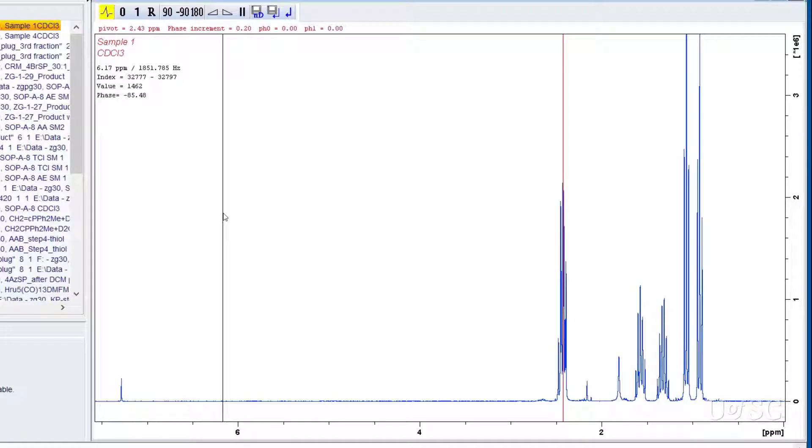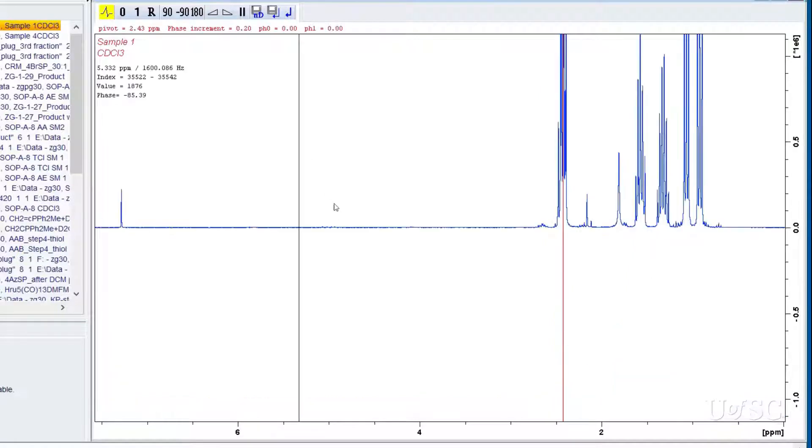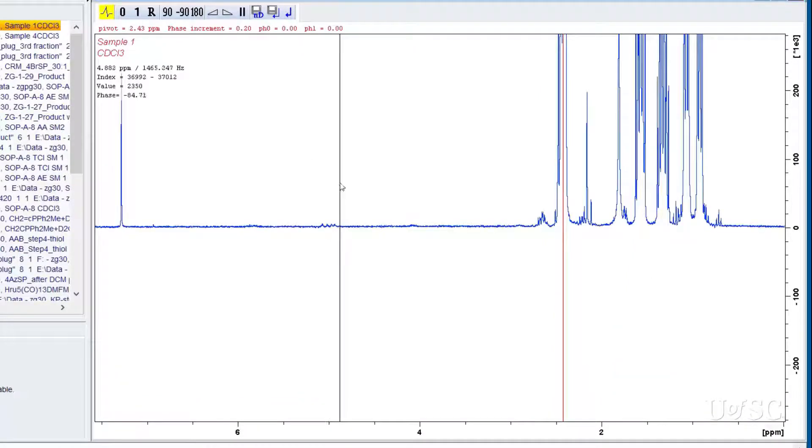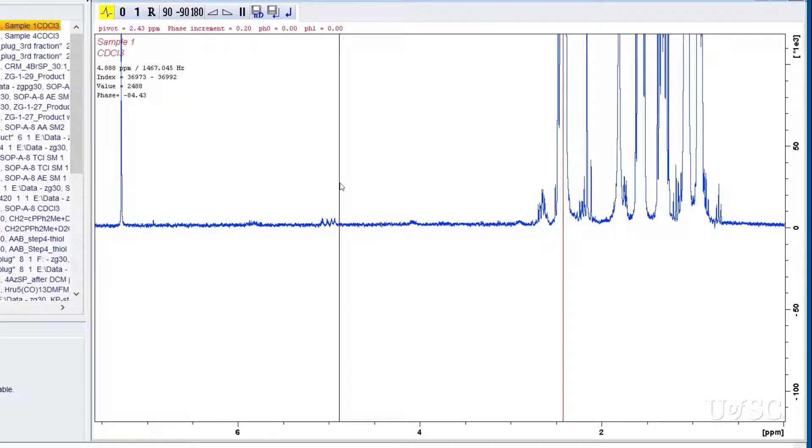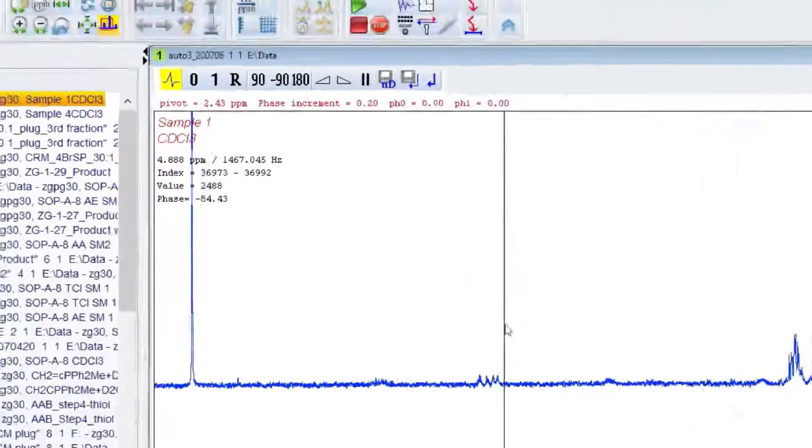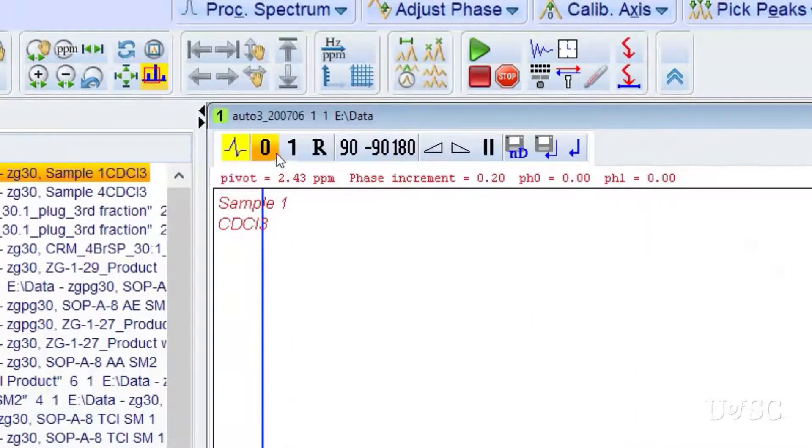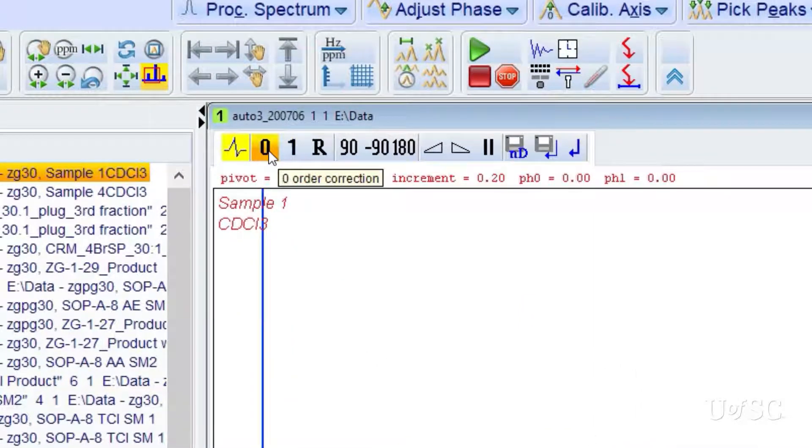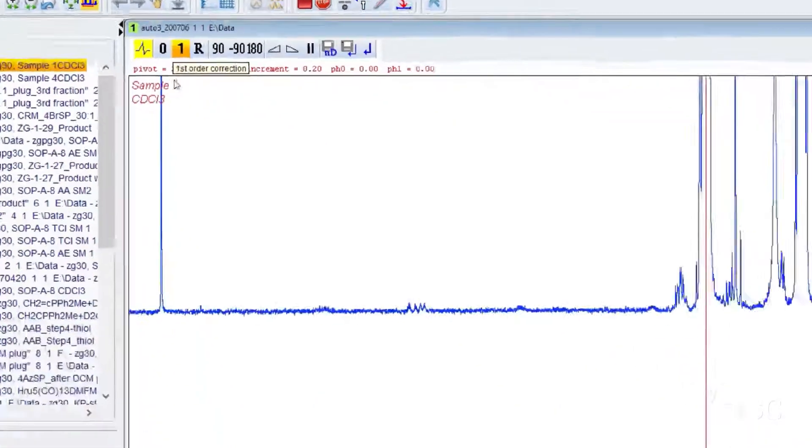Phasing is made easier if you blow up the vertical expansion and raise the spectrum into the top position with the upward pointing arrow on the main button bar. Manual phasing is usually just a two step process. Each step is defined by the two buttons labeled zero and one. They represent zeroth order and first order phase correction and will be made clearer in the following demonstration.